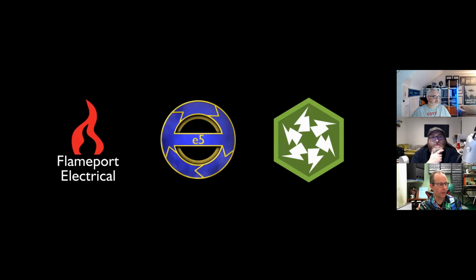And then we've got, in addition to that one, will a TT style earth have a reliable reference to neutral of the supply? Well, it will. That's done back at the transformer of the supplier. And if it's in island mode, then there's that switching device which connects the neutral and earth together when it's in island mode. It may also be in here. There you are.